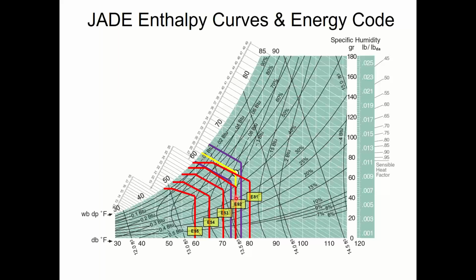So essentially, I'm going to recommend that you pick curve 2. That's almost the code compliant line. There's no line that's exactly code compliant, so I got to choose 1 or 2. 2 is the most code compliant in my opinion. Plus, I don't want 80 degree air, so that's the one I'm going to pick.